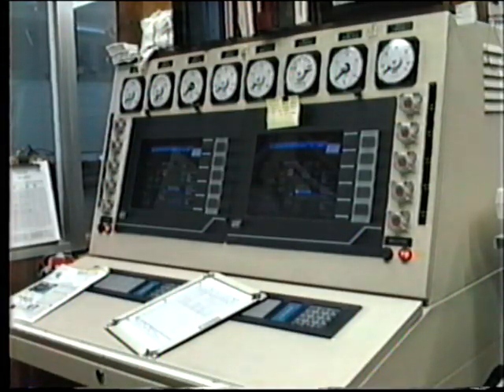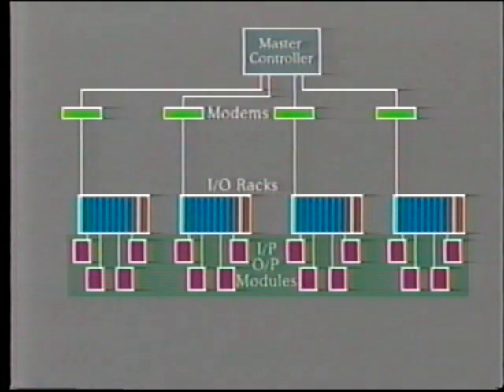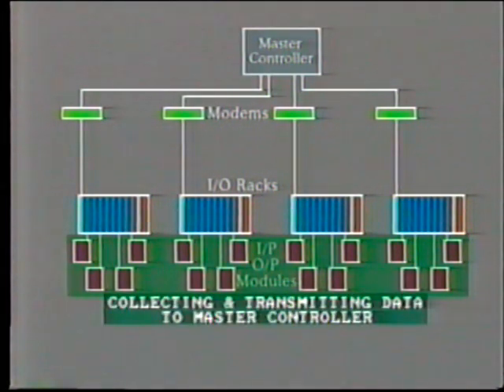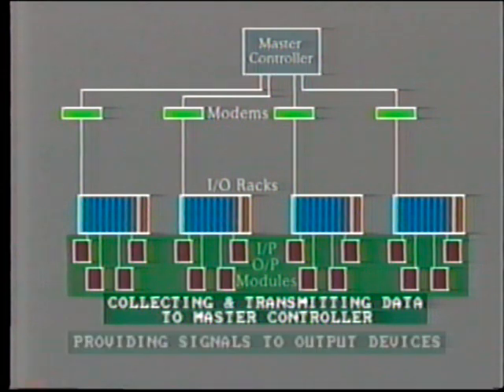To power this, a remote I/O driver circuit board would need to be plugged in to the master controller at the sending end. So now, with this arrangement, we have a large number of input modules spread over a wide geographic area, all collecting data and transmitting this to the master controller when addressed. In the same locations, we have output modules, which are providing output signals to control devices when instructed by the master controller.